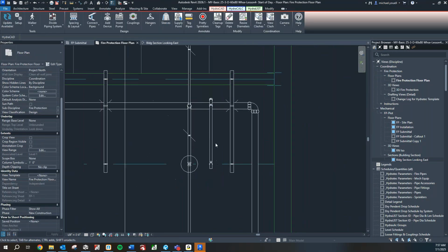You're pretty handy with that, Michael. Have you done any seismic bracing before? Yeah, I'm based out of Seattle, so I do it on every project. Okay, and so I think you appreciate why I picked that joist instead of the other one. Yeah, so in the wall. Yeah, in the wall, that's a good reason, but also it's a little bit further away, so the angle is not as steep. So we'll get a stronger brace in that direction.